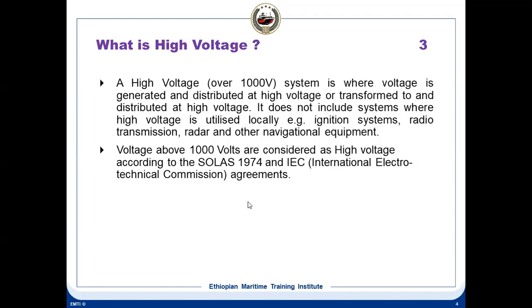Hope you understood this, because we produce high voltage on 440 volt ships also. Like if you see an ignition transformer, that is 13,000 volts or 11,000 volts. So those ships are not considered to be high voltage. Even bow thrusters: on 440 volt ships also, you have a step-up transformer which gives the bow thruster high voltage, but they are not considered to be high voltage ships, because there is no high voltage generation and distribution. So where you have high voltage generation and distribution, those are the high voltage ships. Voltages above 1000 volts are considered high voltage according to the SOLAS regulations 1974 and IEC. So any voltage more than 1000 is considered high voltage.